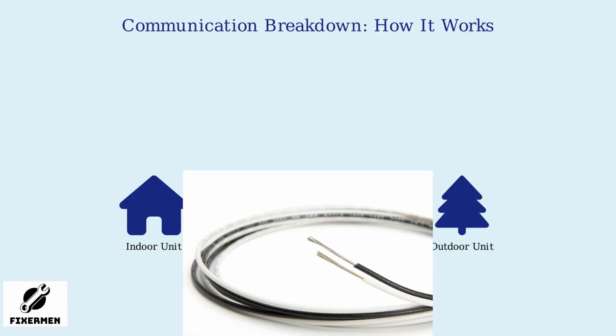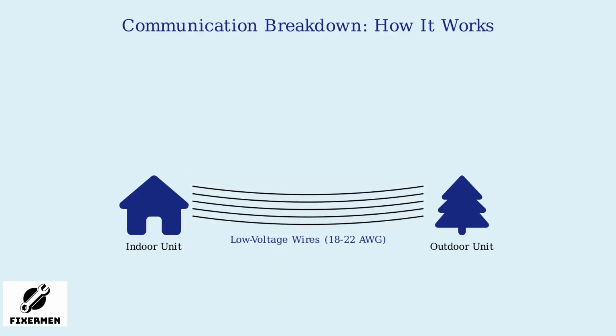When this happens, the system shuts down automatically to prevent potential damage. This is a common issue in split-system air conditioners and heat pumps. We'll break down the causes and fixes next. Amana HVAC systems use a serial communication bus with low-voltage wires, typically 18 to 22 gauge, to link the indoor and outdoor units. This creates a reliable connection for data exchange between the two components.